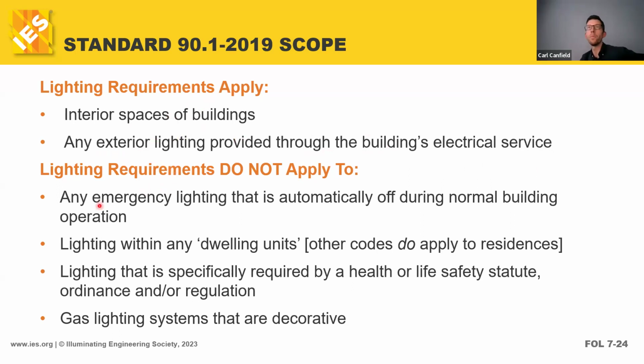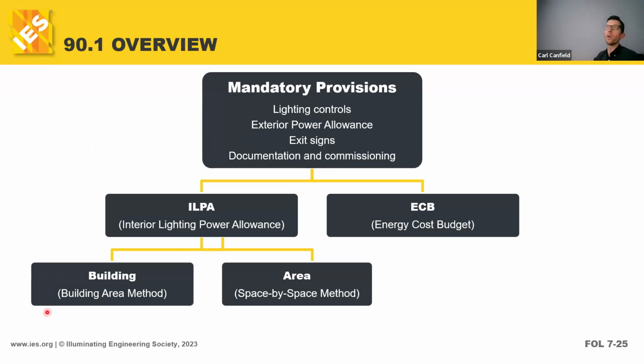What it does not apply to is emergency lighting that is automatically off. There are these certain specific exceptions. So big picture, energy code applies in certain applications, but there are other applications, emergency lighting, dwelling units, basically apartments or condos, where the energy code just doesn't apply. It's either not reasonable, not feasible, or it would be unsafe in the case of emergency lighting. So keep in mind that while code applies to 95% of spaces, there are some pretty important exceptions where it does not apply. Knowing the exceptions is just as important as knowing the requirements of the code itself.